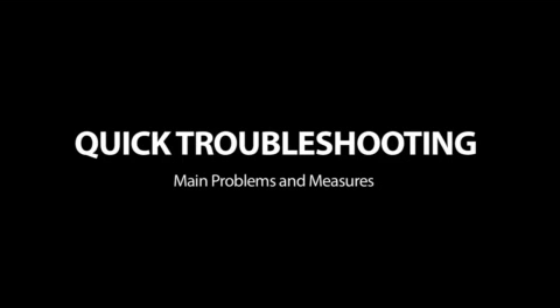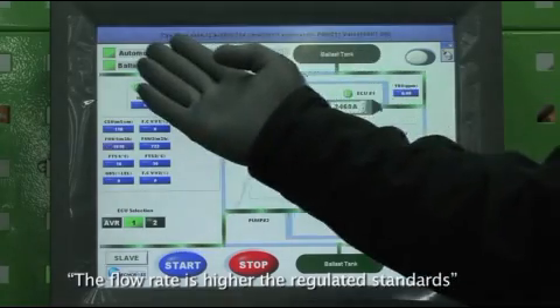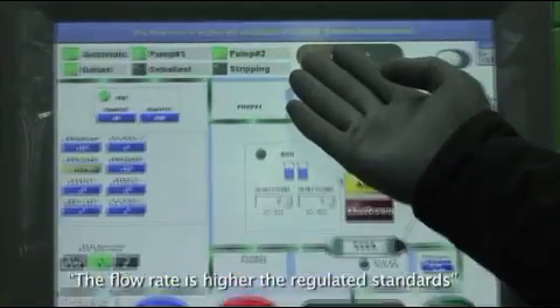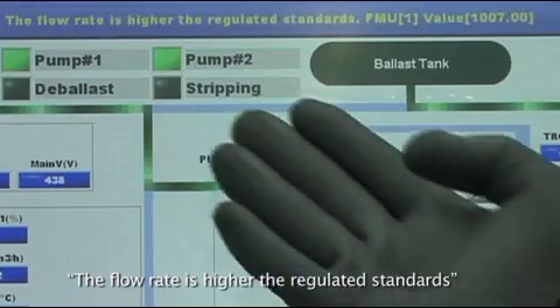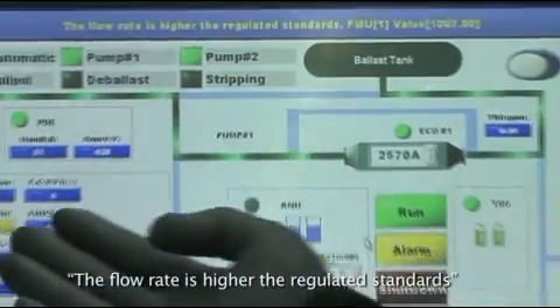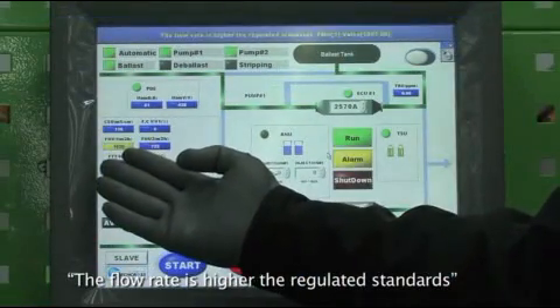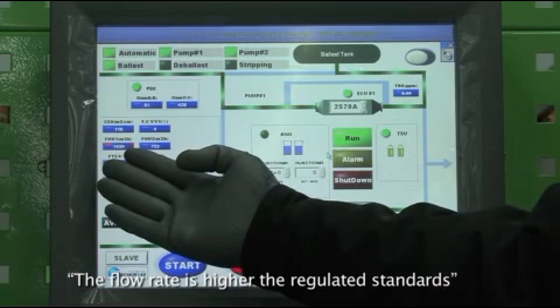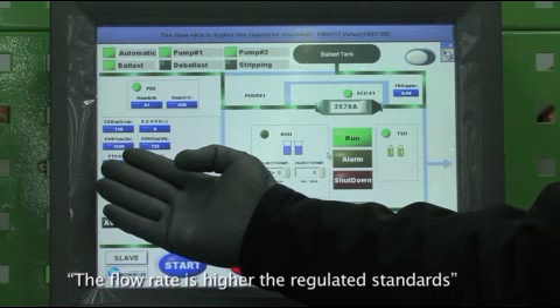Quick troubleshooting. 1. Main problems and measures. Problem. ECS shuts down 1 minute after alarm message. The message "The flow rate is higher than regulated standards" appears. Reason. When flow rate is above the normal range. Normal range, 10% to 110% of pump capacity.